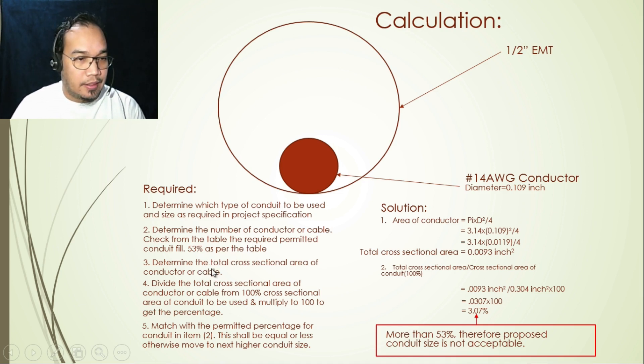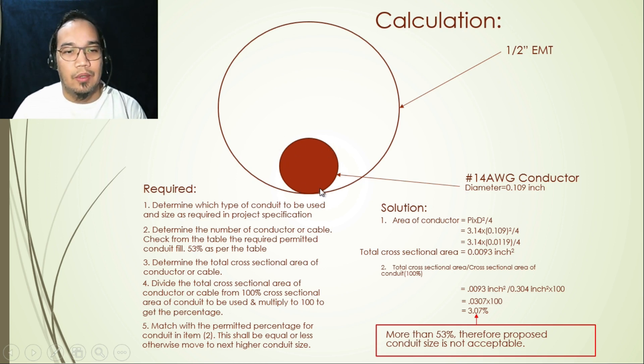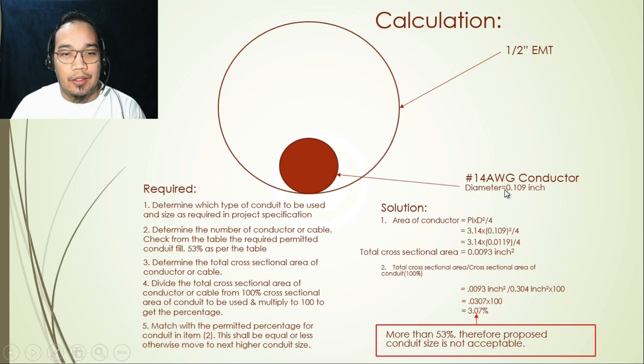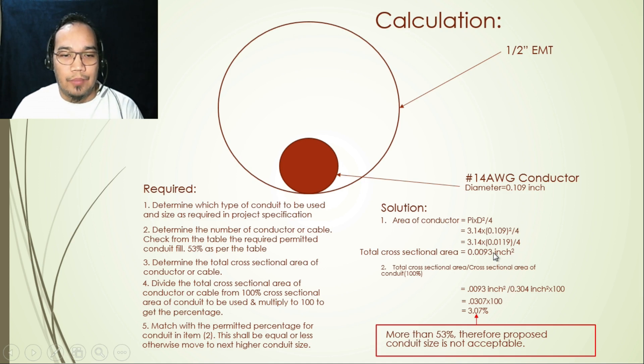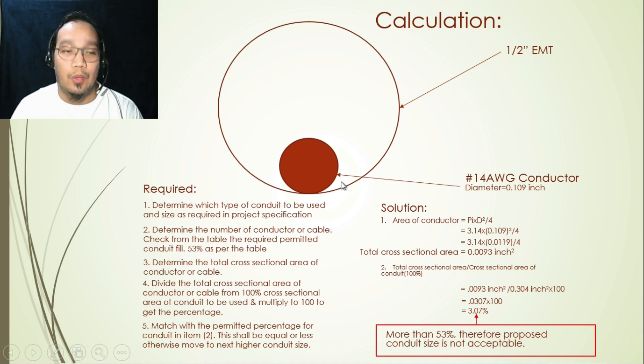The next step is to determine the total cross-sectional area of the conductor or cable. In this example, we have a number 14 American Wire Gauge conductor with a diameter of 0.109 inches. The area of a circular conductor is π × d² / 4, which gives us 3.14 × (0.109)² / 4, resulting in a total cross-sectional area of 0.0093 square inches for this one conductor.